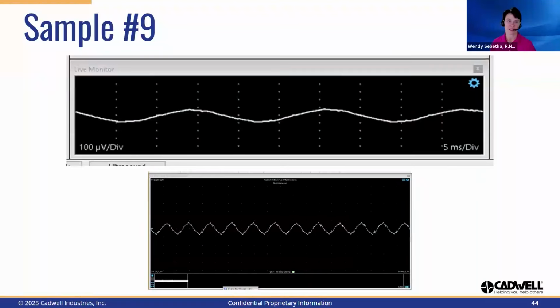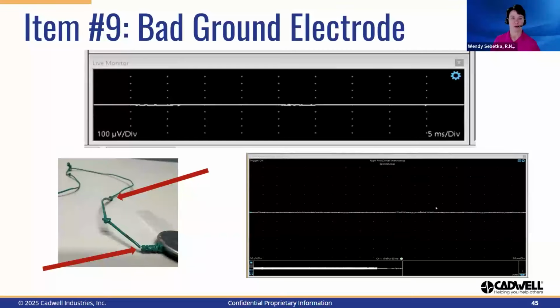Sample number 9 is our final sample and has been an ongoing issue reported by the physician. Key observations note a consistent sinusoidal appearance with superimposed small rhythmic spikes. Again, I suspect this to be a non-physiological issue in nature. As the first step of troubleshooting, all electrodes were visually reviewed. Visual inspection of the ground electrode showed the wire was not only visibly frayed at the neck, but also had multiple tight knots causing kinks in the wires. The ground electrode was replaced, and the issue was successfully resolved. Most noise issues are able to be resolved using these troubleshooting techniques.